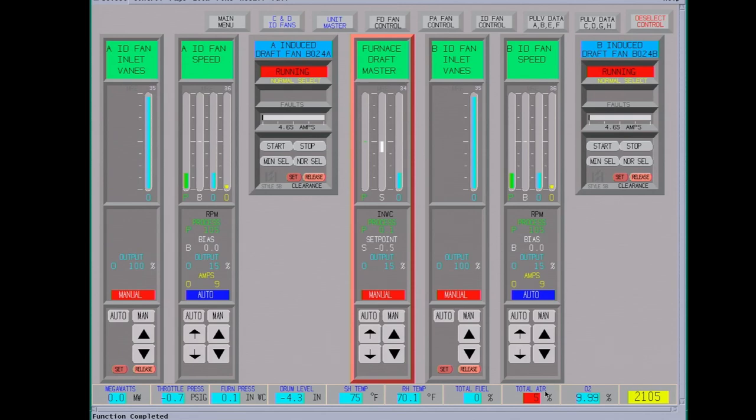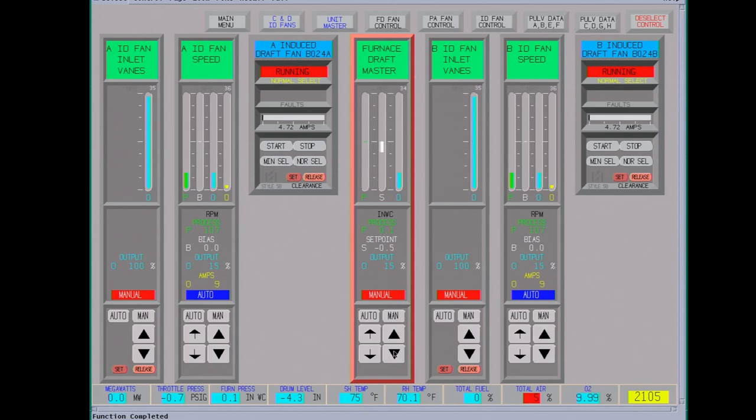Total air flow down here 5%. We have to be above 30% to purge the boiler. And it's also a trip point. If it drops below 25% when you're running, it will trip the boiler. It's for protection of having a furnace without enough air for a complete combustion. It can develop explosive gases in there and cause a furnace explosion.